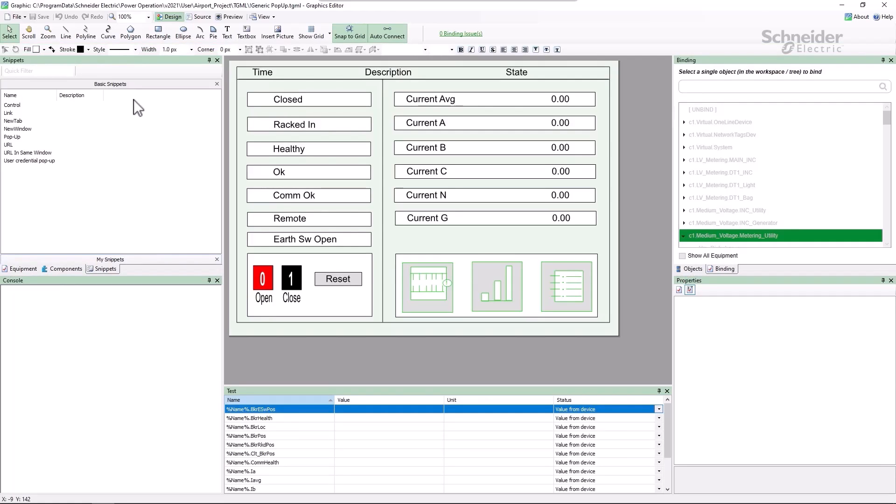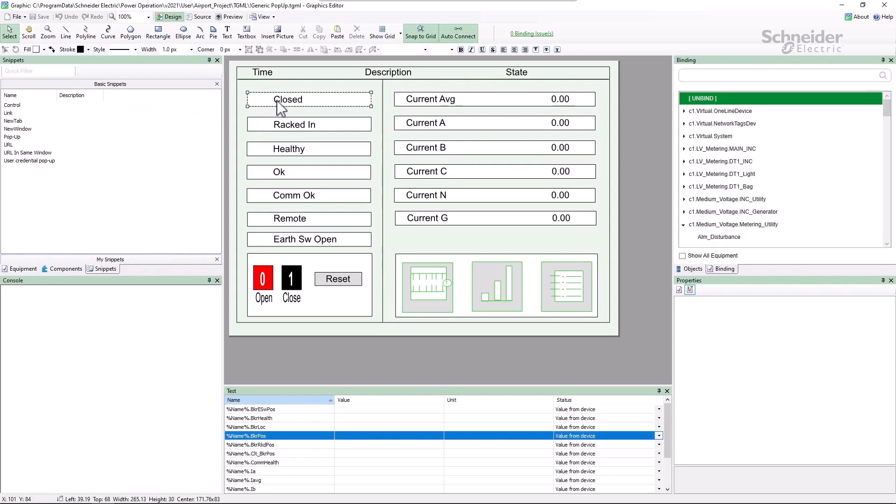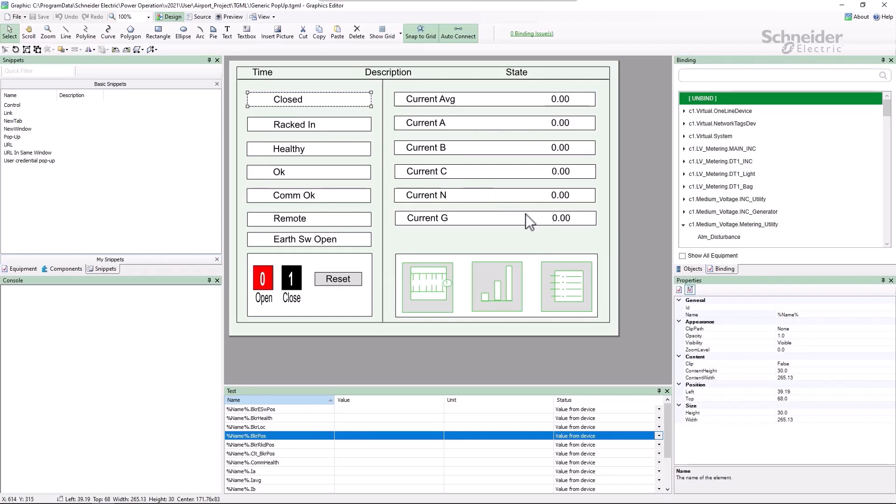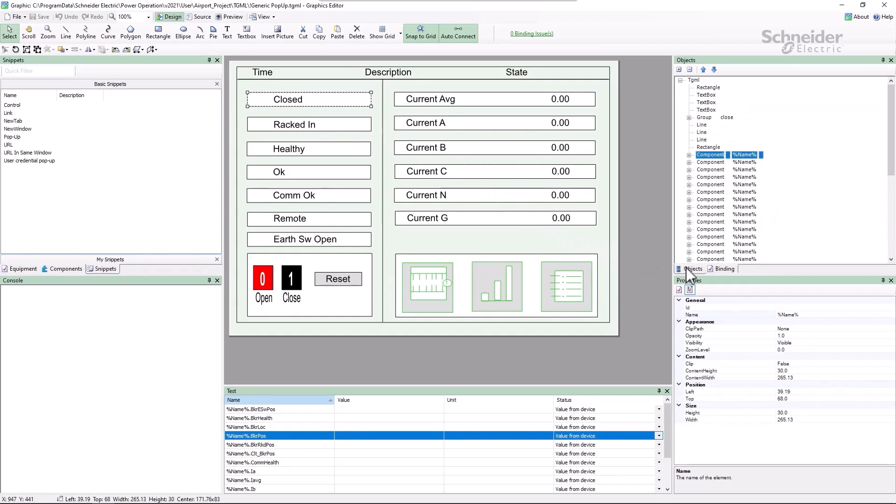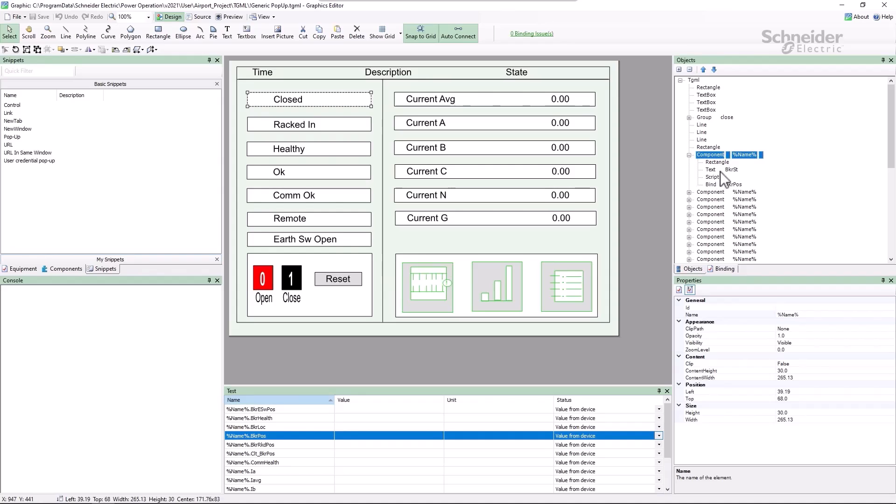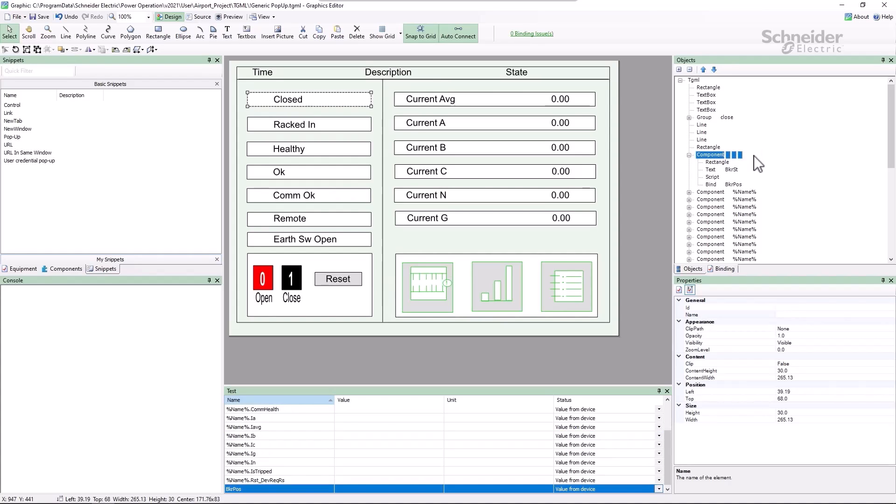As is, the page will map all points to the meter. The scripts in these components handle changing the values and indicators, including changing visibility if the binding fails. This is what we need to change. Recall that binding takes the component name and attaches the bind name below that. So to change this binding, I'll remove the component name and change the bind substitution to closed.